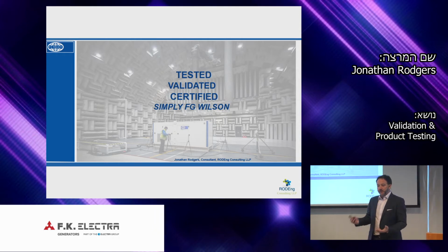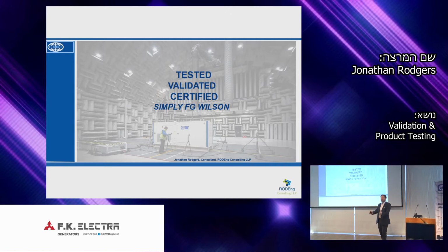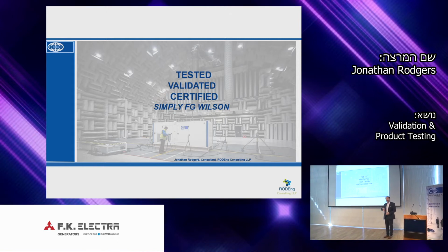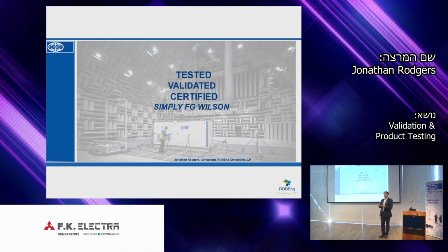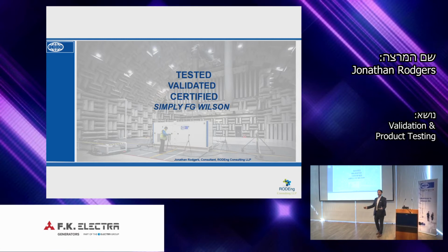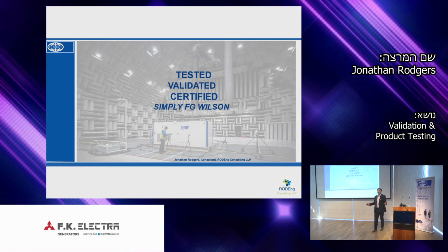So with our FG Wilson product, it is not a matter of taking an engine and an alternator, bolting them together and seeing what happens. Everything is designed and modeled through our new product integration process, our NPI. Once our Perkins engine is finalized in its design and becomes a released engine, we work with Perkins to develop the cooling group selections. That cooling group selection occurs at FG Wilson, and then through our combined test facilities, we test and validate that system.